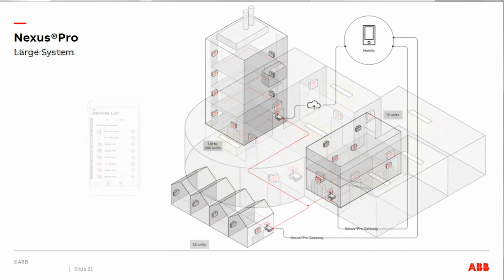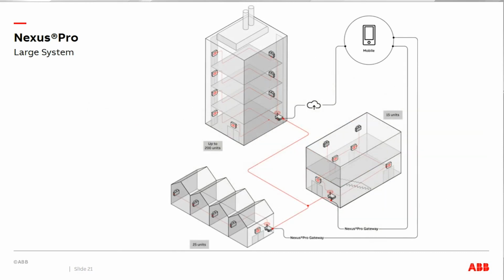Those are very simple models of buildings, but how scalable is Nexus? Nexus can do anything from a single emergency lighting fixture and a gateway, working all the way up to, well, there is no limit. There's no limit to the number of gateways or fixtures you can have in a building connected to a particular client's application. The only limit we have in place is 200 fixtures per gateway.